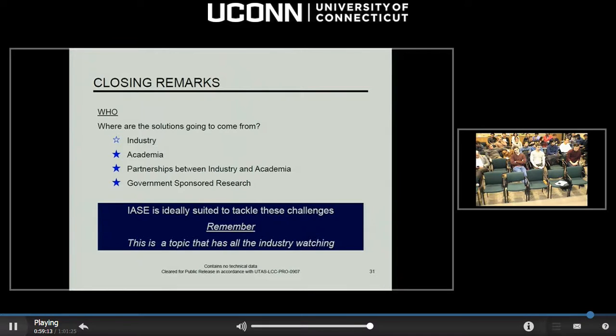I believe you have a global reasoning system that looks across multiple things, and I have to do it in a time frame that doesn't allow the faults to propagate or occur, so that I have failure modes. One thing I didn't talk about is confirmation time—just because I get a blip on a sensor doesn't mean I call a fault. It has to be there for a particular amount of time. That time is very important because it tells me my false alarm rate.